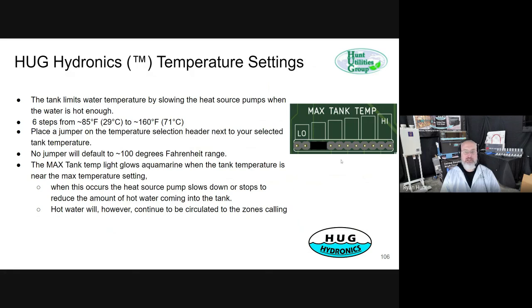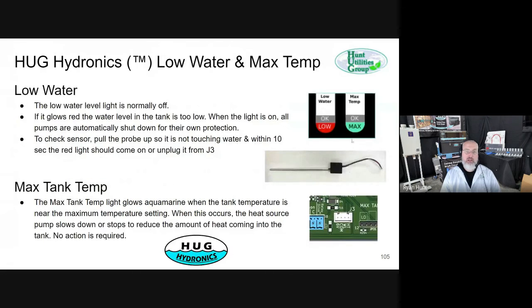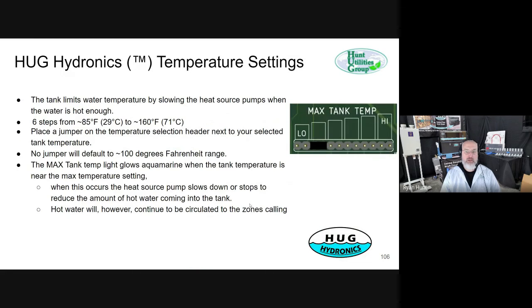As it approaches that tank temperature, that blue light, the max temp light, will turn on, and it's not a problem. It's not an error of any sort. It just says, hey, we're happy with the tank temperature now, and then it starts to slow down the pump that goes to the boiler. It'll slow it down and turn it off, and then the boiler is just maintaining the temperature in the tank at that point.